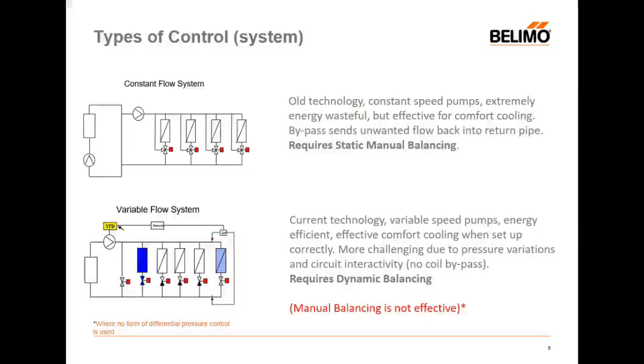When I was younger, quite a bit younger, I must say, constant flow systems were the norm because variable speed technology was expensive and constant speed pumps were employed. And that led to constant volume systems, where any energy not required at the coil is simply bypassed by a three-port control valve. Now, of course, that needs to be balanced. So we'll need some manual balancing valves in each of the circuits, and we maybe need a manual balancing valve in the bypass, which is going to replicate the pressure drop of the coil when we do bypass in order to maintain the balance. That's old technology.